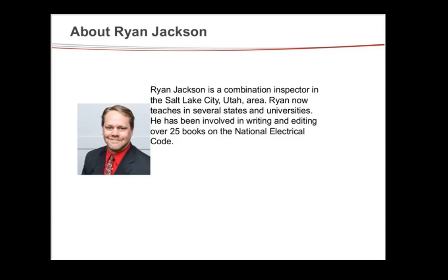In addition to that, you also have 110.16B, which is for the service disconnect of commercial buildings. It says, more specifically, if the service disconnect is rated 1,200 amps or more, you not only have to have the sticker, it also has to comply with the new requirements that talk about the clearing time, the available fault current, the voltage, and the date the sticker was applied.